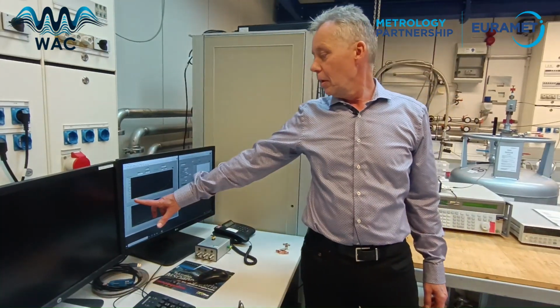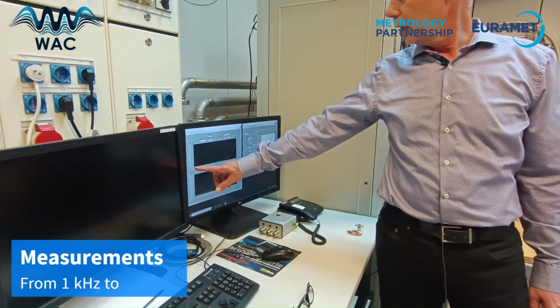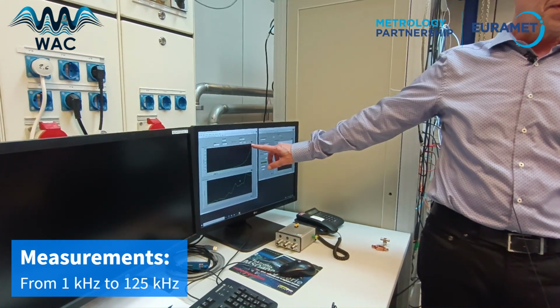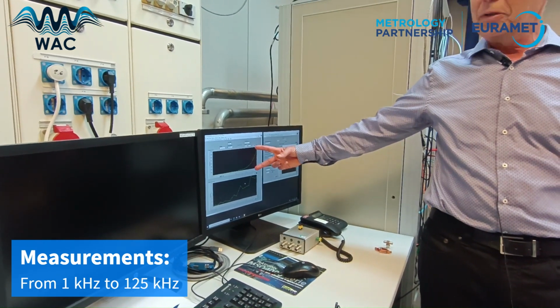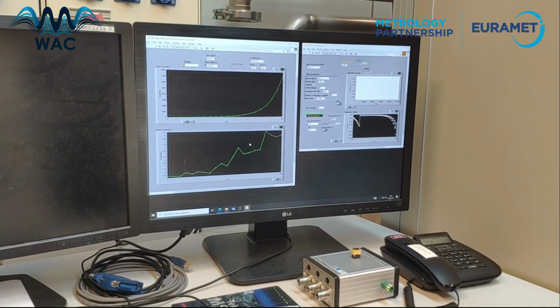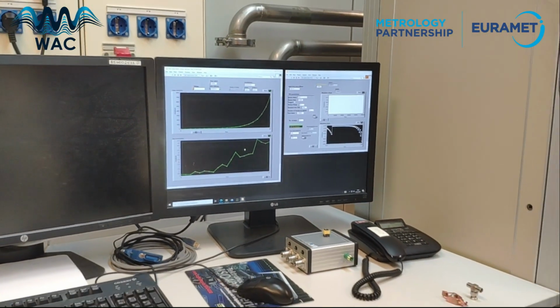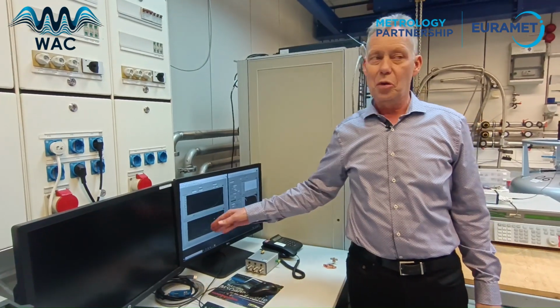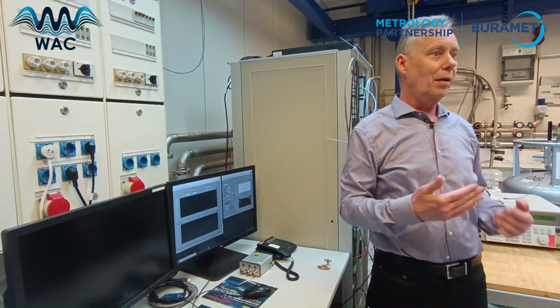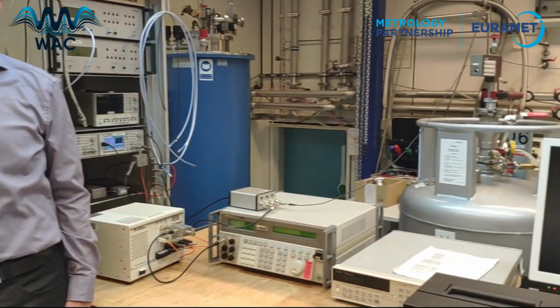Just one measurement has finished. We are covering now the frequency range from 1 kilohertz up to 125 kilohertz. What is plotted is the difference between the two cable lengths we are measuring here. As we assume the measurement with the short cable is almost within the ppm level, we can directly see the uncertainty which is introduced by the long cable length.